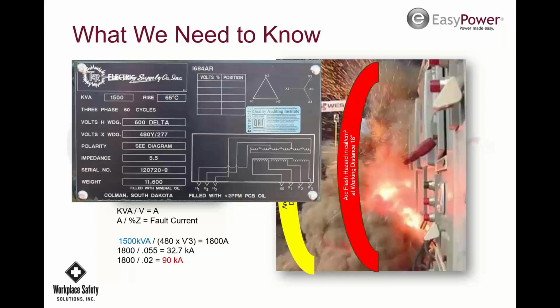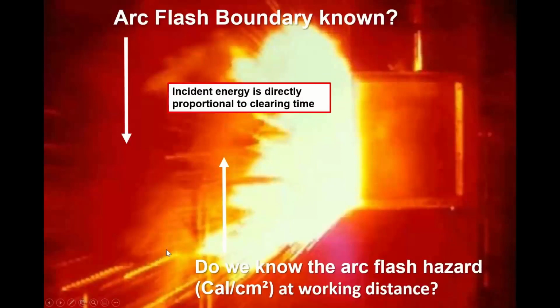So that is an impact from an impedance level of what the arc flash hazard can be as well. So it's again part of your assessment. Okay, so we need to know what this arc flash level is at our working distance, and that's always going to be 18 inches for low voltage. It'll be 3 feet for medium voltage over 1,000 volt stuff, and then our arc flash boundary.